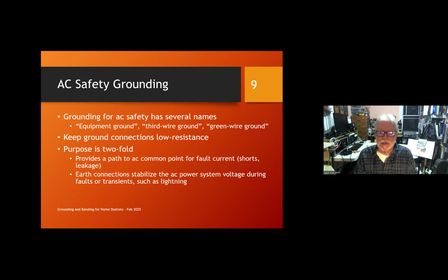The ground connections have to be low resistance, as we talked about before. They have to carry all the short circuit or fault current back to the AC reference point so that the protective devices, circuit breakers or fuses, will open up and remove power from the affected circuit. This is to prevent fires, which is why your ground connection has to be low resistance.